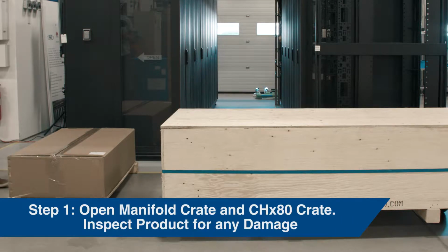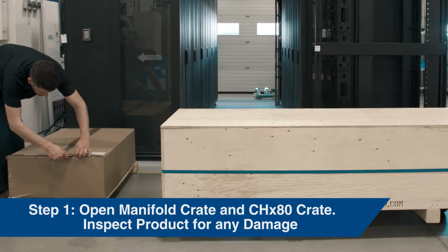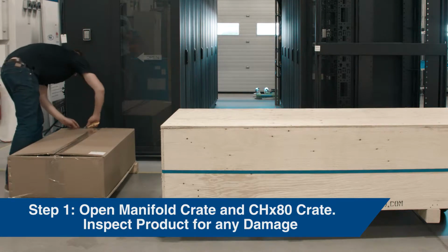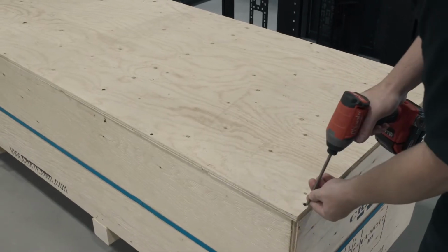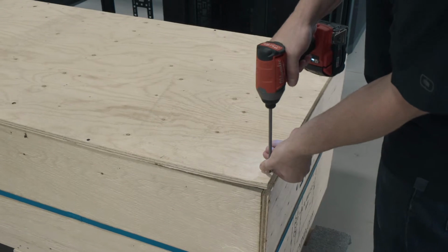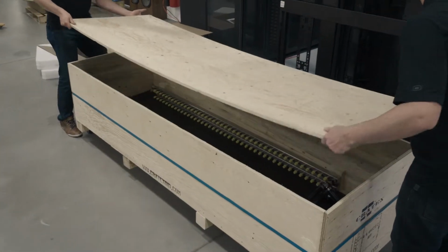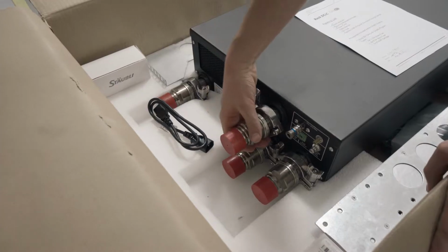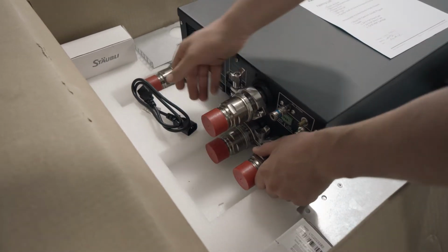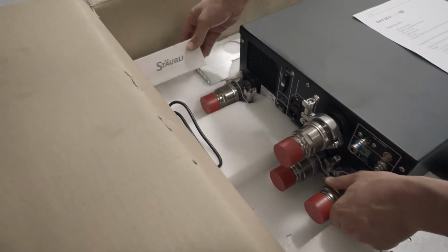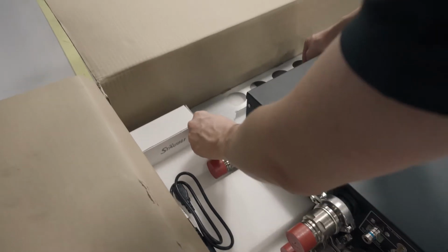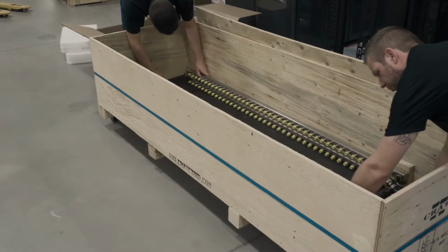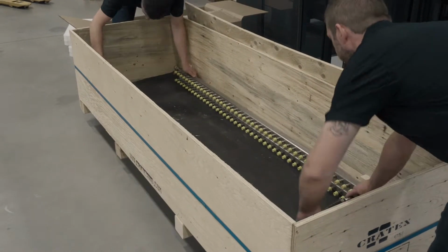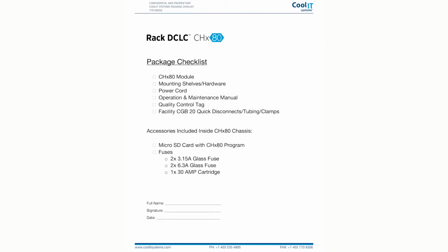Step 1. Open manifold crate and CHX80 crate. Inspect product for any damage. Remove the lid from both the manifold and heat exchanger crates using your drill and number 2 Phillips bit. Immediately inspect the manifold and heat exchanger for any obvious shipping damage. In the unlikely event that damage is found, you must stop installation and contact CoolIT for further instruction. Finally, review the included package checklist to ensure all parts are accounted for.